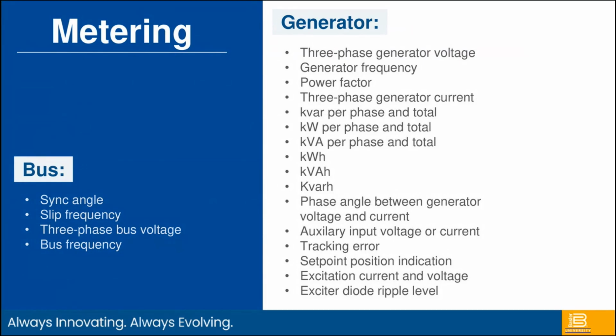From a metering standpoint, the digital products will meter pretty much anything we're looking at from the regulator, or anything that we can calculate. So on the bus, if we have a bus input, we can look at the sync angle, slip frequency, obviously to do our synchronizing. Bus voltage, bus frequency, and the generator, we have obviously voltage, frequency, power factor. We can also do some internal things like a tracking error or output, the control output, or the amount of output we're putting out into the field, set point position indicators, and so on and so forth there.